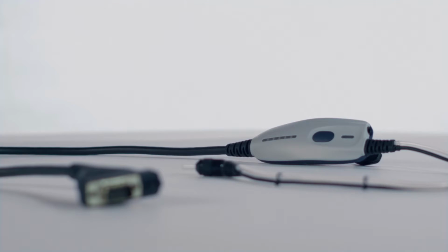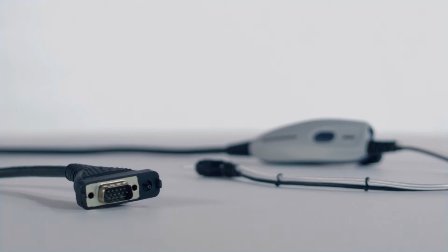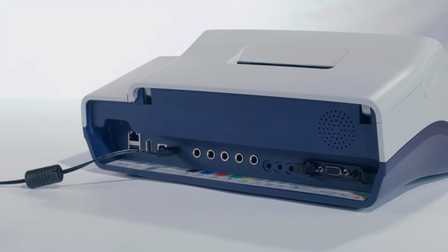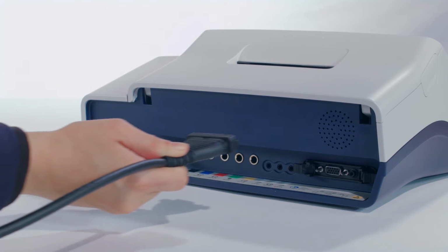Use the diagnostic probe with the touchTymp to perform advanced testing. The probe comes specifically calibrated and can be used right away. Attach the probe by gently pushing the connector into the jack labeled probe.